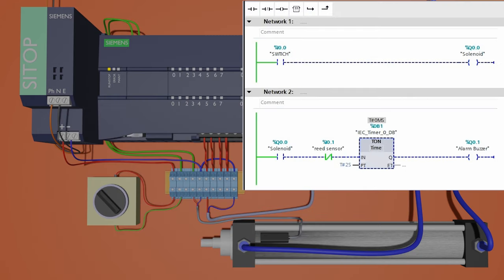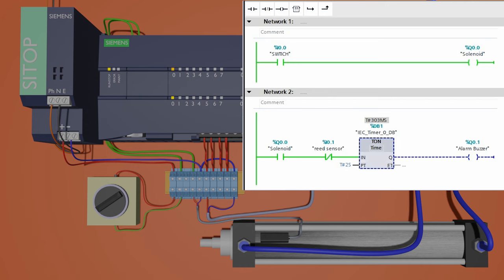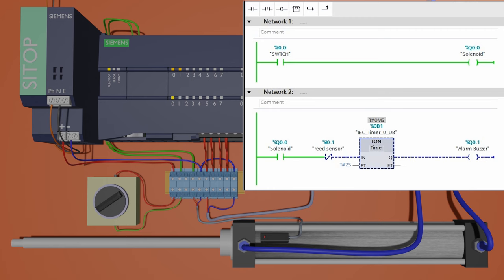Now let's test the program. As we turn the switch on, it will activate the solenoid Q0.0 and the solenoid supplies the compressed air to the cylinder, and the cylinder shaft starts to move outwards. Once the cylinder shaft is fully extended, its piston position is picked up by the reed switch and its normally closed contact I0.1 opens up and disables the safety timer.